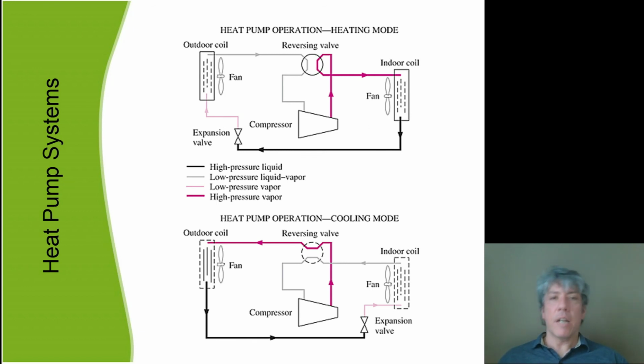So if you stand over your register with an older heat pump, it feels like cold air coming out. It's not. It's actually 85 degrees or so, but as it blows past you, since you have water on the surface of your skin, it feels cold. And people just didn't like heat pumps because it felt like they were cooling the house, not heating it.